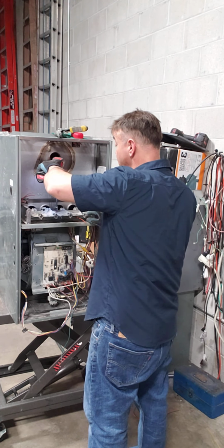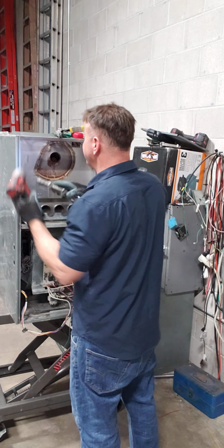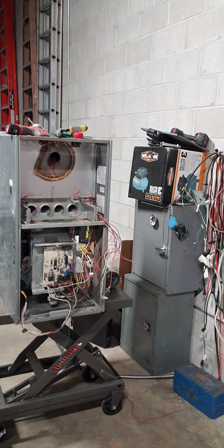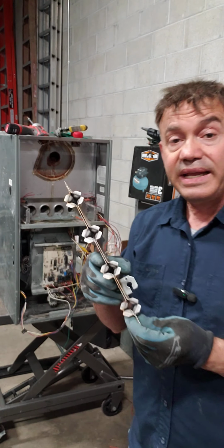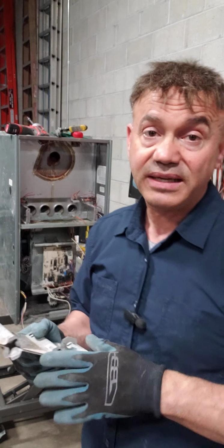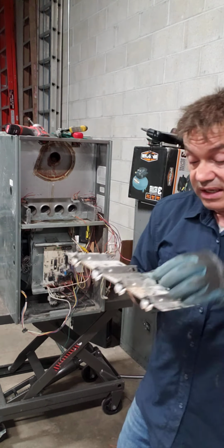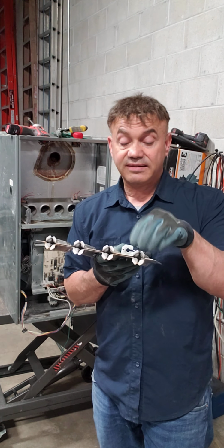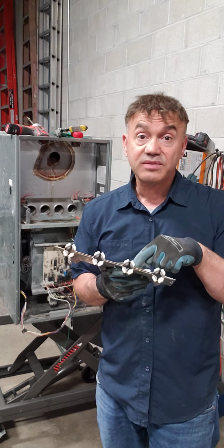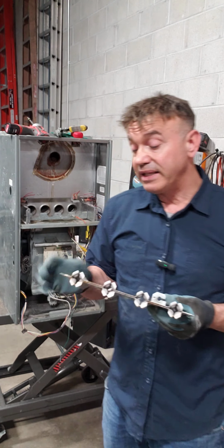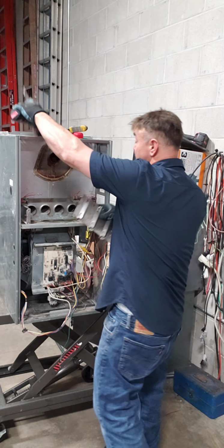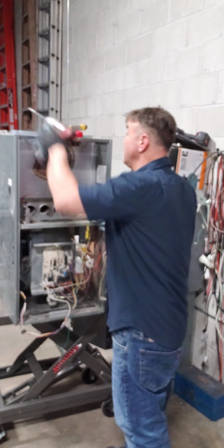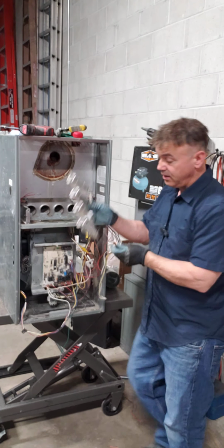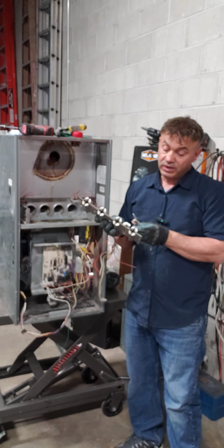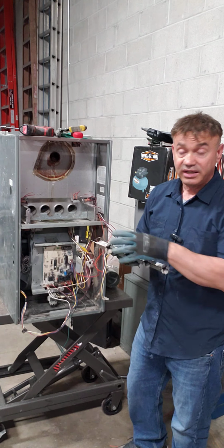Now, the most important part of the burners is here. Basically, there are 4 or 5 screws, as you see. So basically, these are the burners. And as I was saying before, many times, I keep saying it. Sometimes when the igniter fires up the first one, there's a gas pathway. It will ignite the others, and then always the flame sensor, as you see, is always here, right? So you have the igniter here.